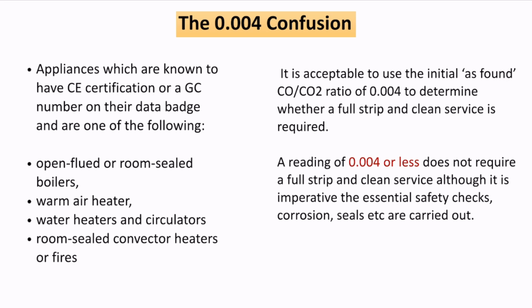It's acceptable to use the initial as found, that means as you found it when you first started working on it, of 0.004 to determine whether a full strip and clean service is required. A reading, in the case of what I explained to you, the CE certificate and the types of appliance, of 0.004 or less does not require a full strip and clean service, although you must carry out the essential safety checks on the appliance itself.